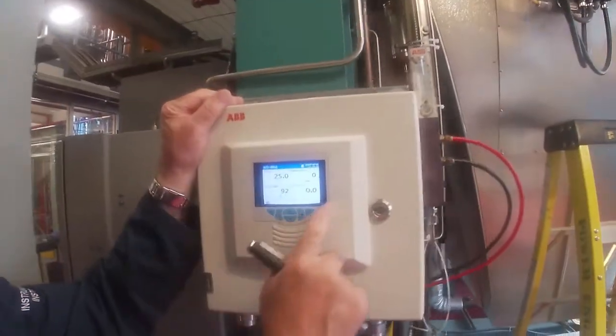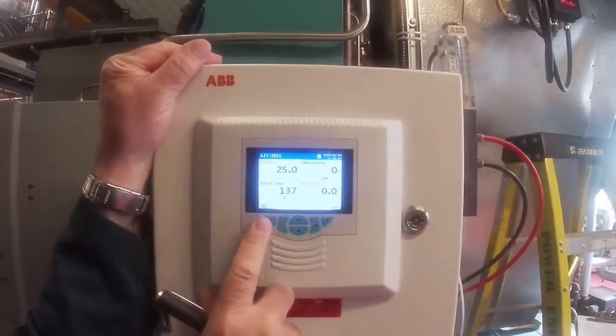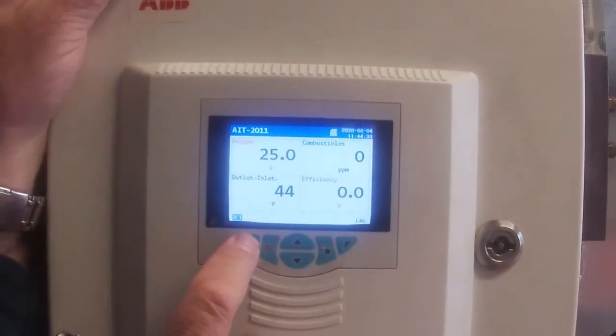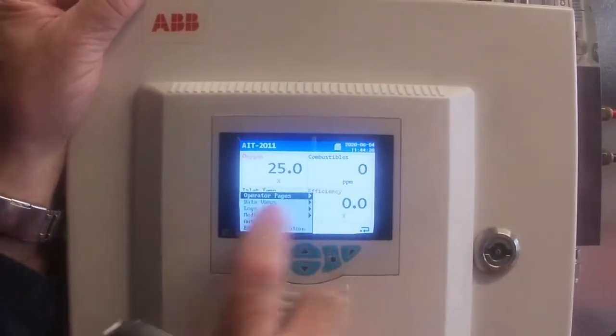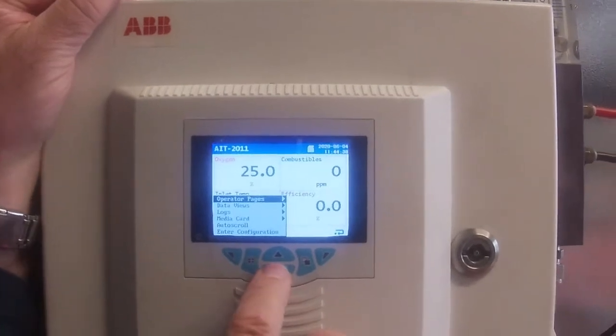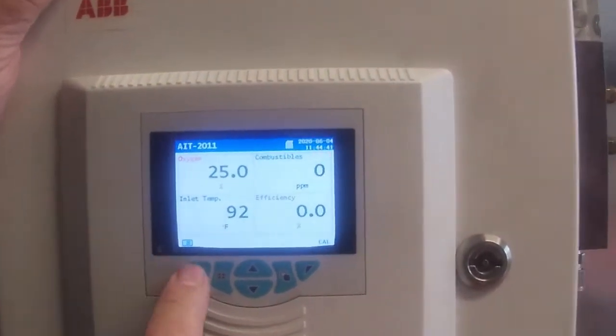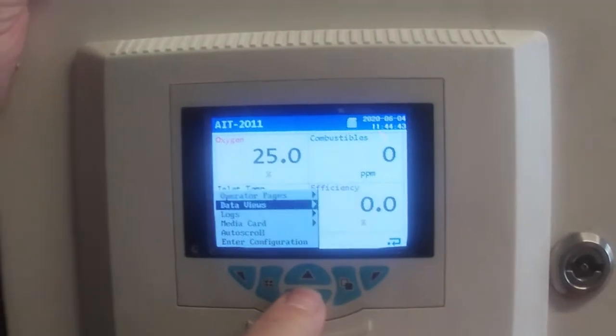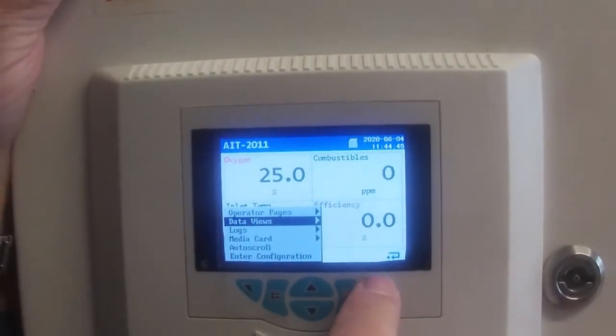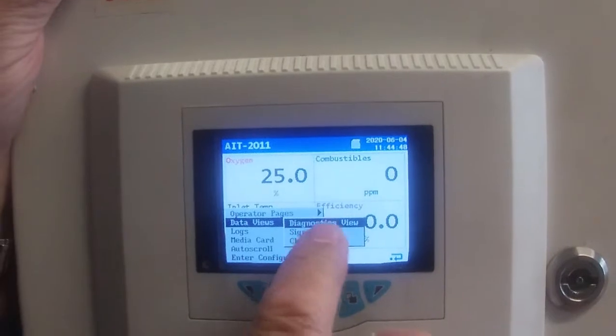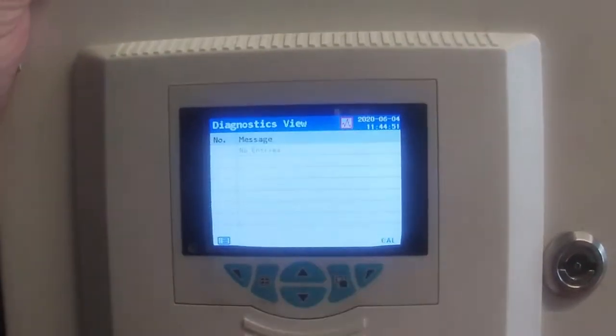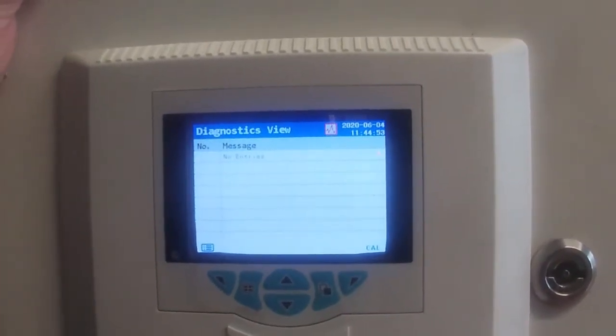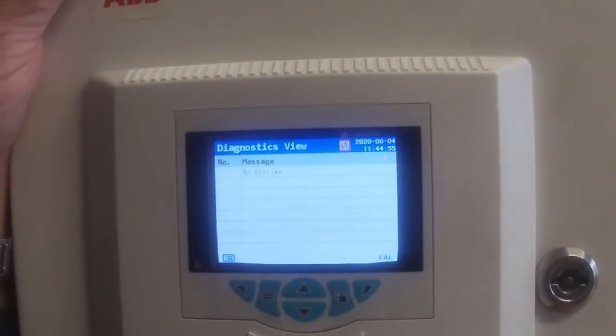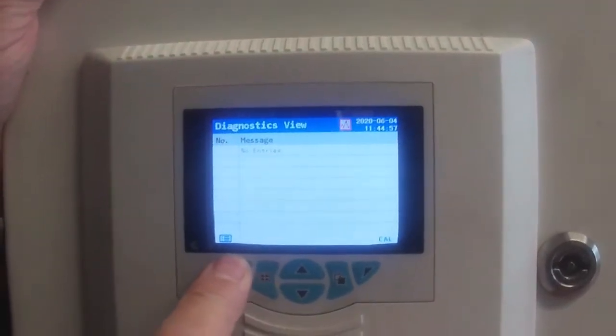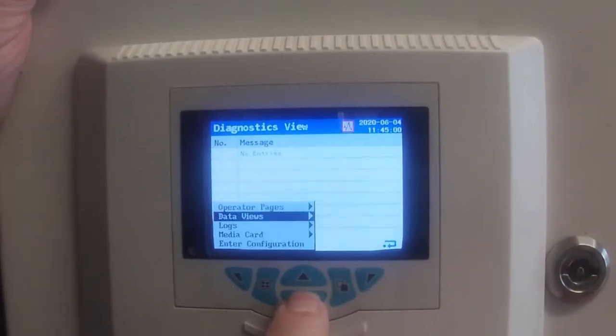If we take a look over here, we want to calibrate this thing. There's a button there which looks like little pages, and right now I'm on the operator page, but I can go down and I can look at data views, and in here, if I select it, I can look at a diagnostics view, and if I look at the diagnostic, there's no entries. This thing has never had any problems. Right now everything is running fine. There's no problems with the analyzer itself.